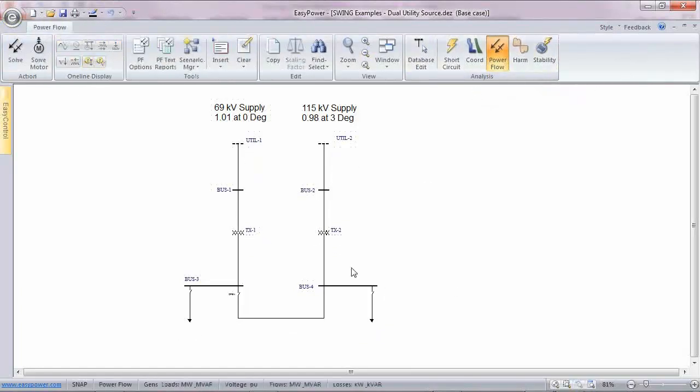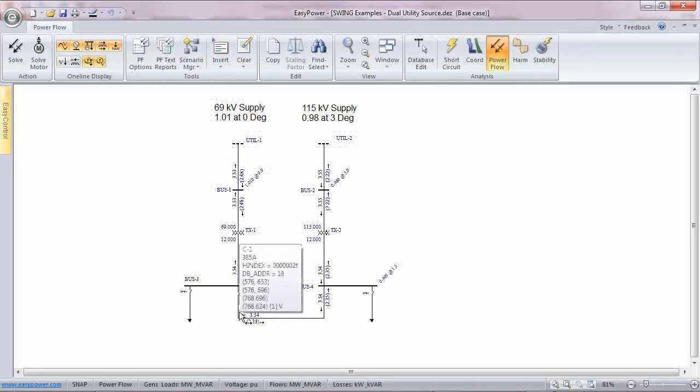Notice if I were to come back here and add a quick switch onto this load, just to show this without any load, you will see solve, no load, no load, close the switch, you will see the circulation all by its lonesome because there's no load being served. Okay, so this is a case where we have two sources, and the little comment that I made earlier was, please don't connect them up together.